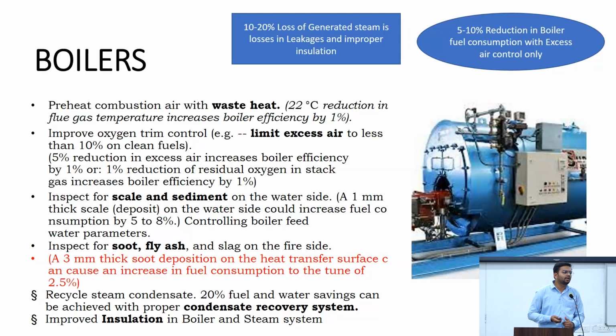When we supply hot air to the boiler, we need less fuel to heat that air up to the combustion temperature. So that is one ECM we can implement. There is also a major implementation of excess air control. Carbon needs oxygen for proper combustion, and that oxygen level we need to maintain in the boiler. If we supply less air than required, it generates incombustible gases.